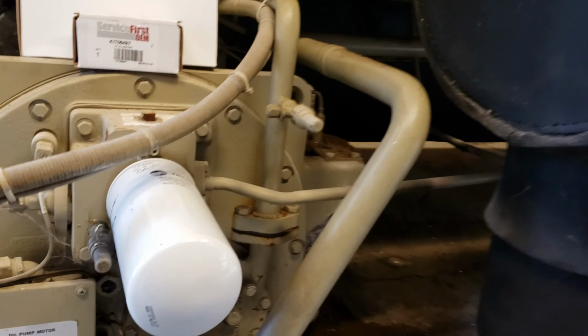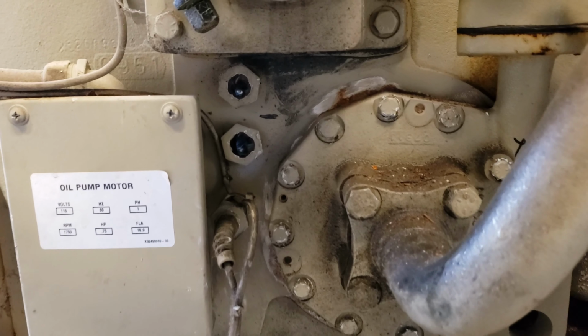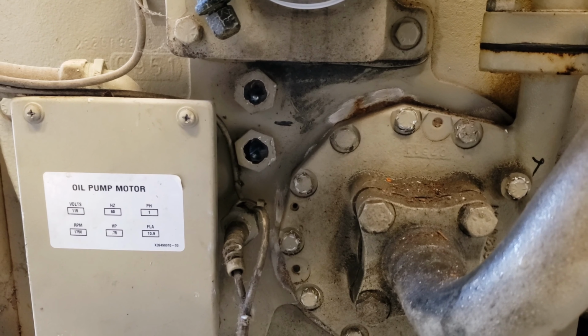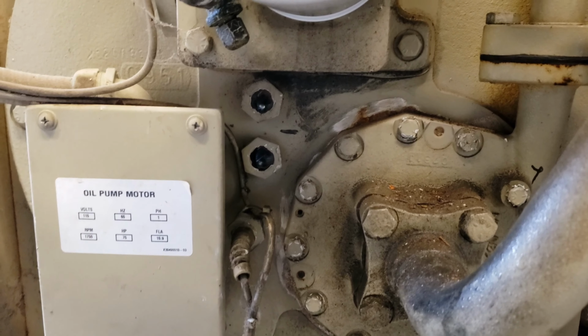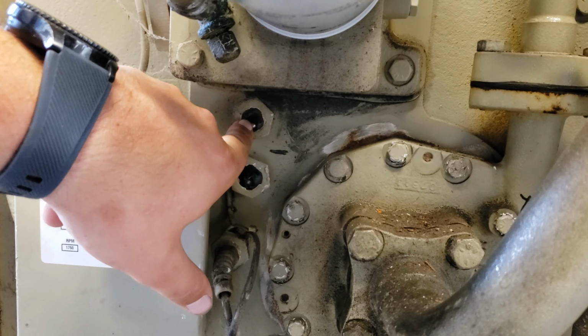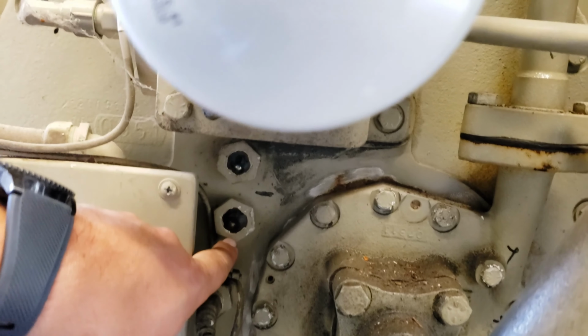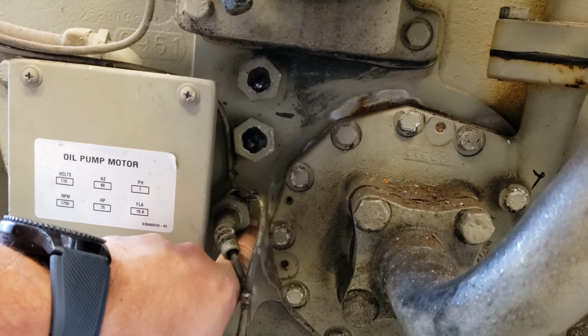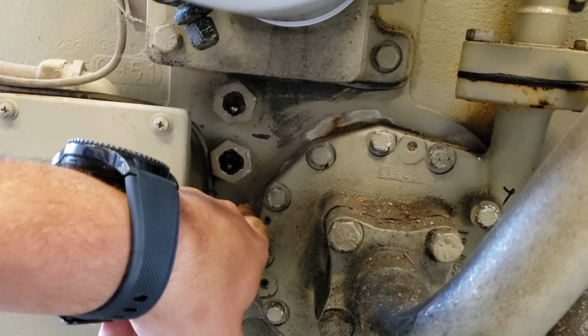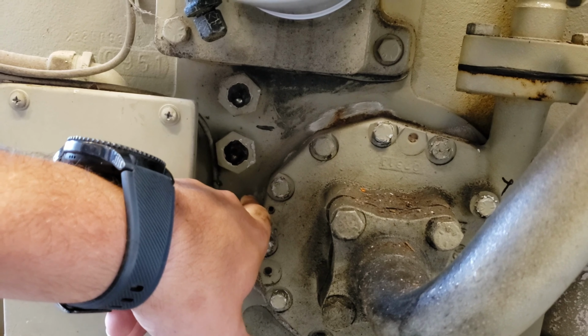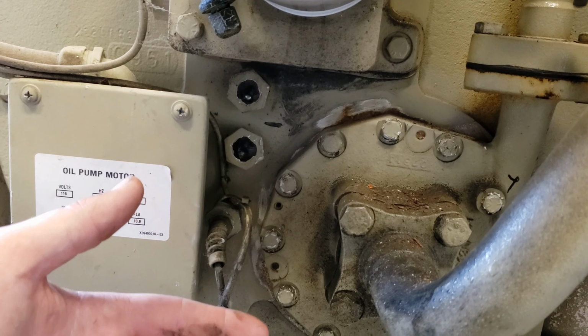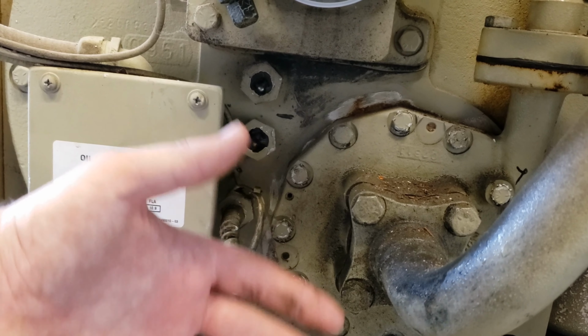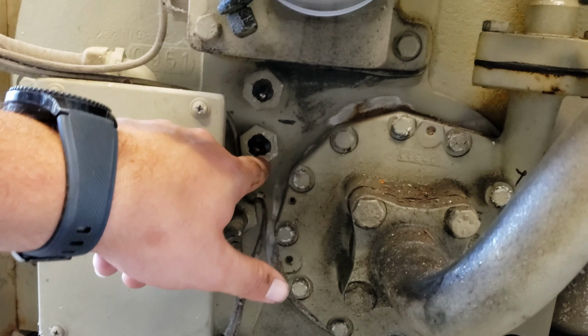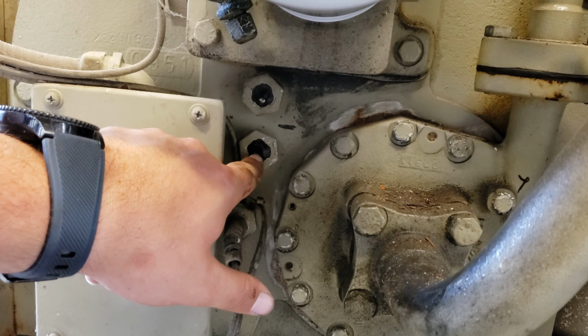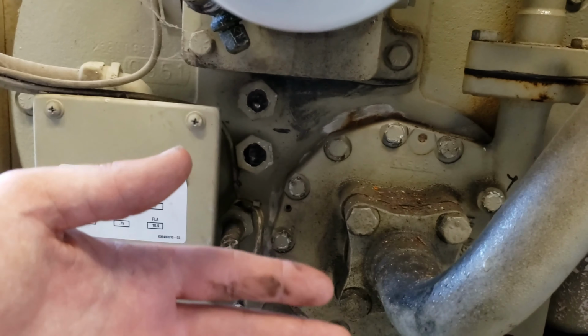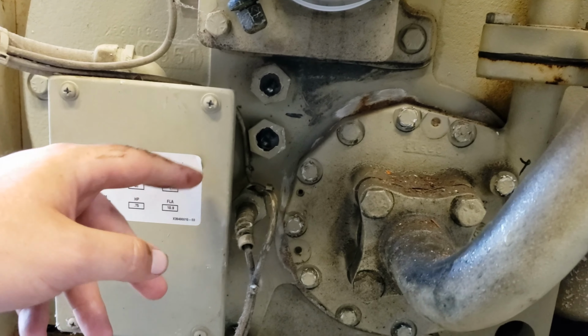Another bonus is by fixing everything and getting it right. Those BBs are stuck in the bottom, but you won't be able to see it with this camera. When I first got here, our oil level was down to about right in here, pretty low. It was so low I was worried about even running it the way it was. The customer approved adding 5 gallons, so I did, and that got me to right in the bottom of the sight glass, and I was okay with at least putting it in operation at that point.